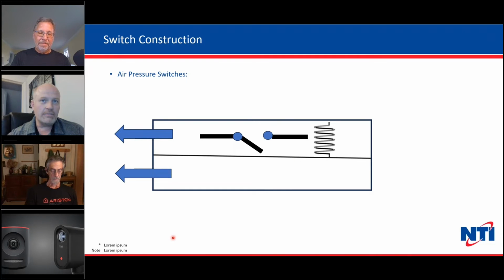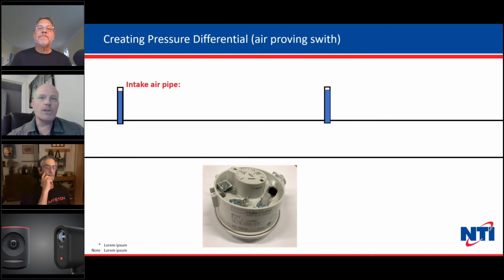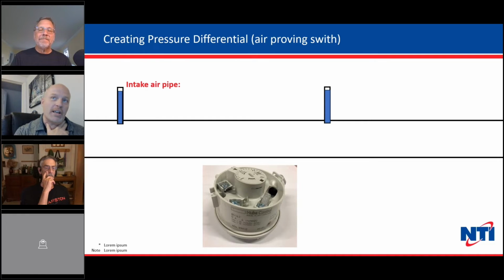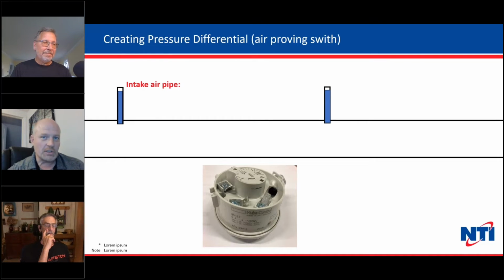So anytime you see two ports connected on that switch, the intention is that both ports might be negative, they both might be positive, but while the boiler is doing something, there will be a difference between them, and either that difference needs to be great enough to trip the switch, or it needs to be not great enough to trip the switch, depending on the application. So this is creating pressure differential using the air proving switch.